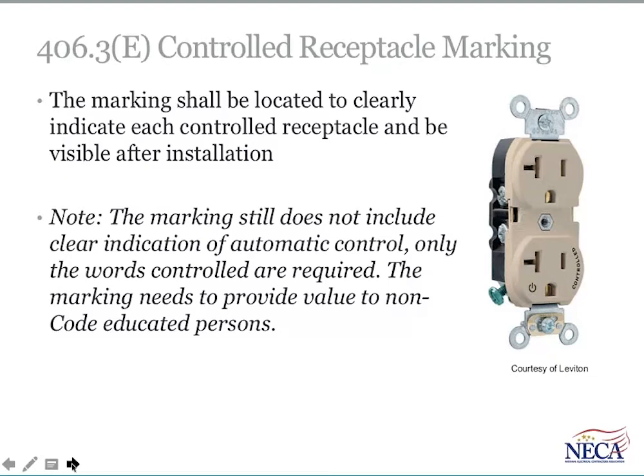So essential loads that you want to remain on all the time, you would want to refrain from plugging them into a controlled receptacle. You want to make sure that there's power there all the time. So that's the change, to include the word "controlled" in addition to the symbol on the face of the receptacle. Interesting challenges for the code panel because there's not a whole lot of real estate to deal with on the face of the device.